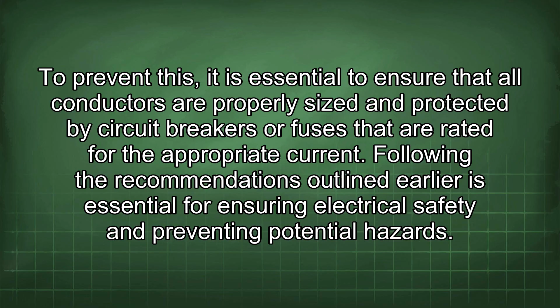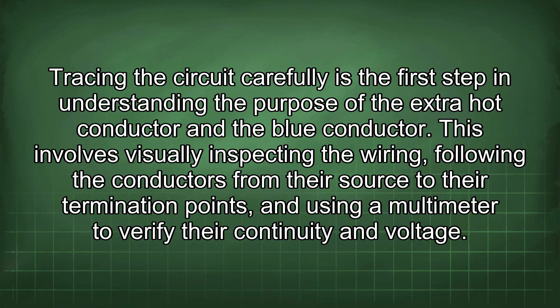Following the recommendations outlined earlier is essential for ensuring electrical safety and preventing potential hazards. Tracing the circuit carefully is the first step in understanding the purpose of the extra hot conductor and the blue conductor. This involves visually inspecting the wiring, following the conductors from their source to their termination points, and using a multimeter to verify their continuity and voltage.